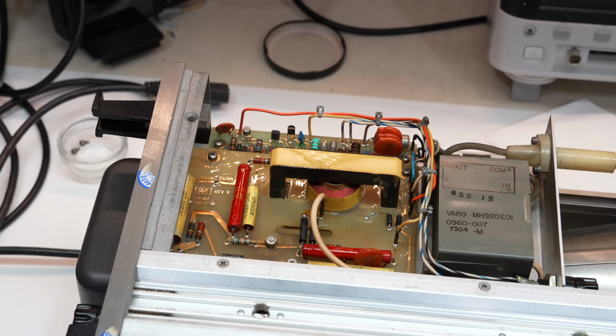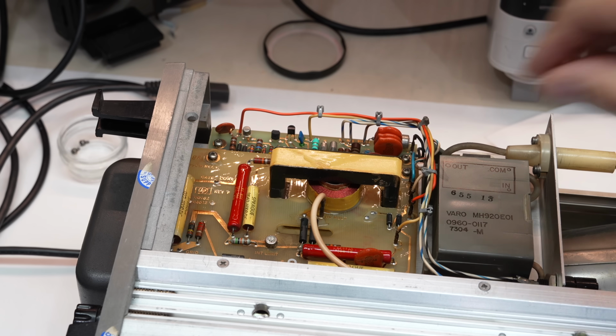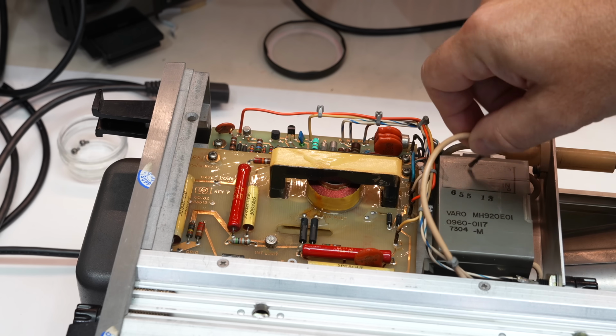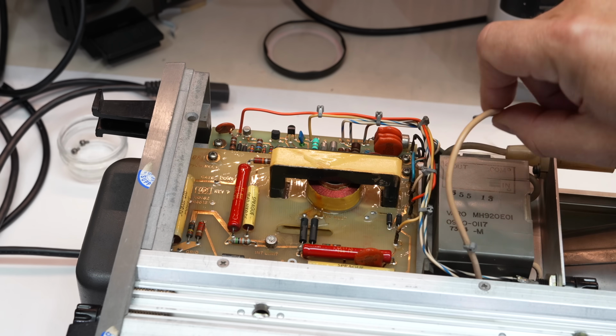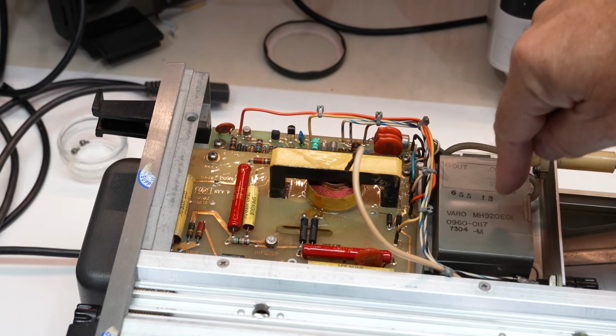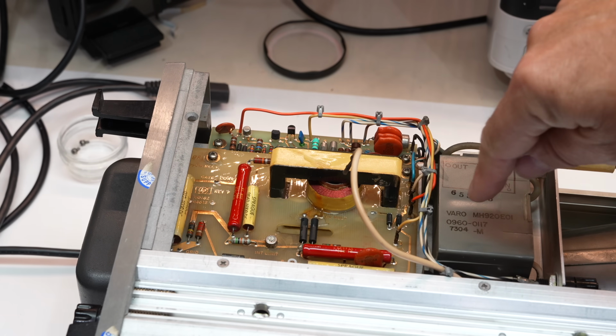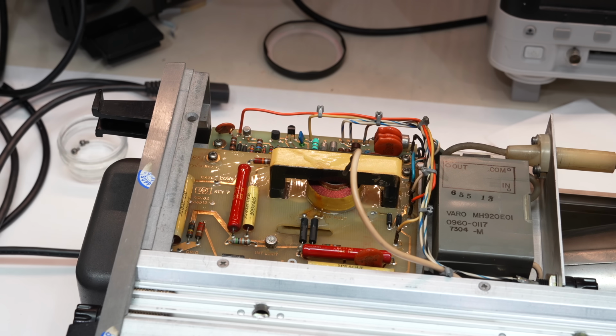Let me show you that in the schematics. Oh, and by the way, the first thing you want to do when checking the power supply is remove this, because this is the power to the multiplier. So it's 3 point whatever kilovolts up to here, and then it goes into the multiplier and it becomes 18 kilovolts, but we don't need it right now.